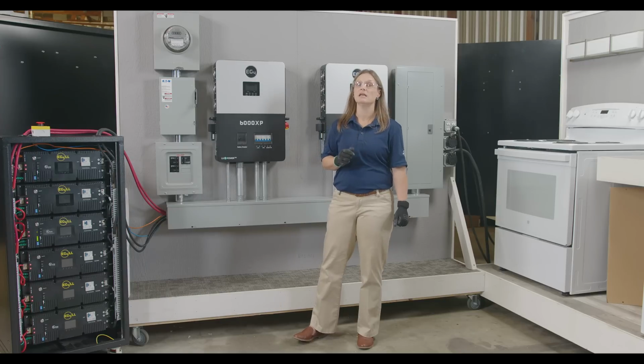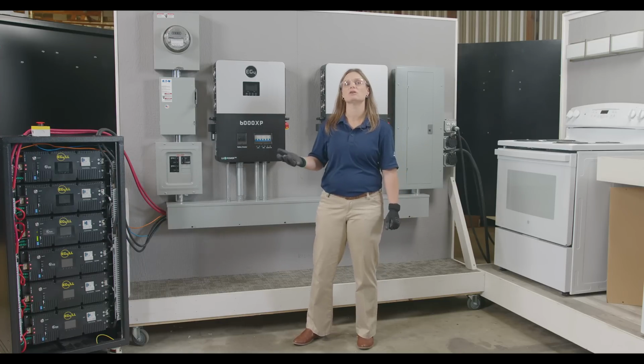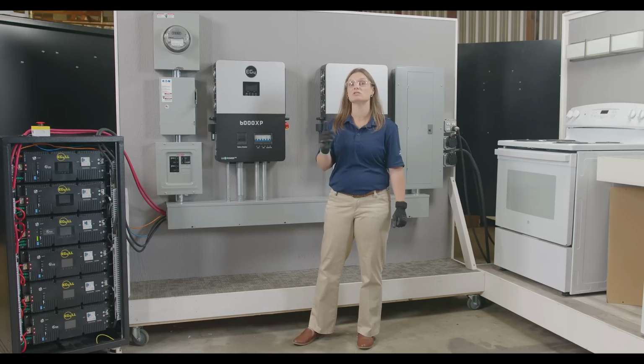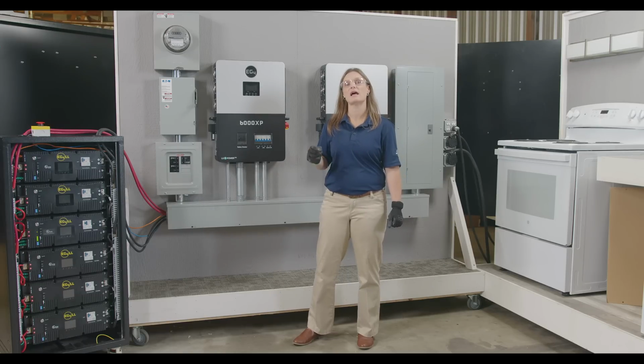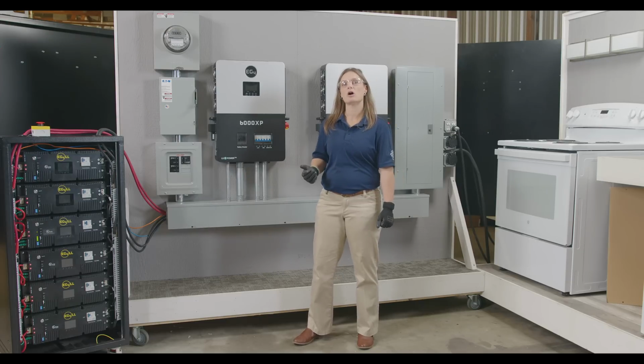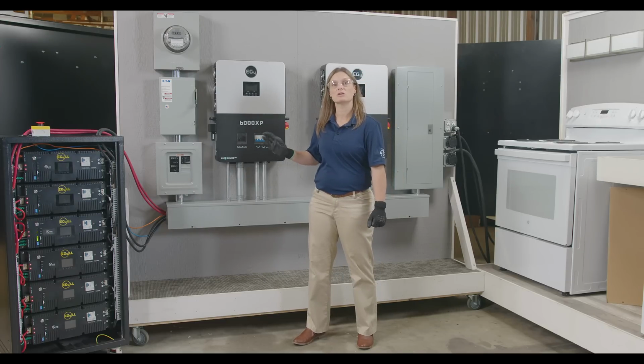But listen up, if you're running multiple inverters in parallel, the sequence in which you turn on those EPS output switches is crucial. You will need to make sure that you flip the EPS output switch on the inverter you want to use as your master first. Then you should be able to turn on the EPS on your other inverters connected in parallel. With all batteries on, make sure the communication works on all units.